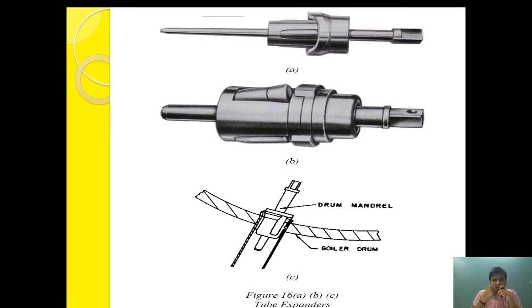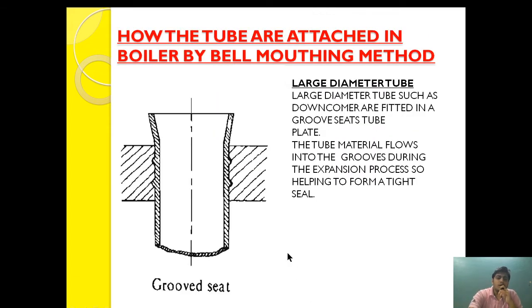As you can see in this diagram, these are the tools used for bell mouthing. First, a mandrel is inserted into the end of the tube, and after that it is opened up. This opening up causes the expansion or bell mouthing of the tube, preventing it from coming out while remaining in service.